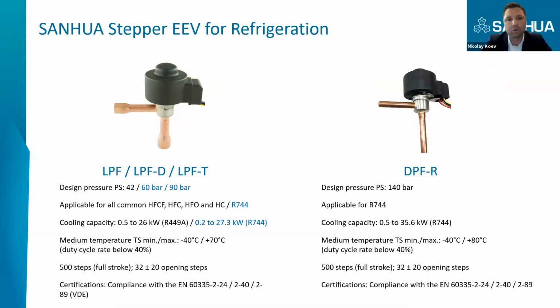This is the tightness. This valve comes with a soft sealing design, which means that when the valve is closed, there is no internal leakage through the valve, and no need to use a solenoid valve before the stepper motor electronic expansion valve, as it was in the past. This is a unipolar stepper motor valve with 500 steps. And we also have a valve, DPFR, with a maximum operating pressure of 140 bar, which is applicable with CO2 transcritical condensing units.